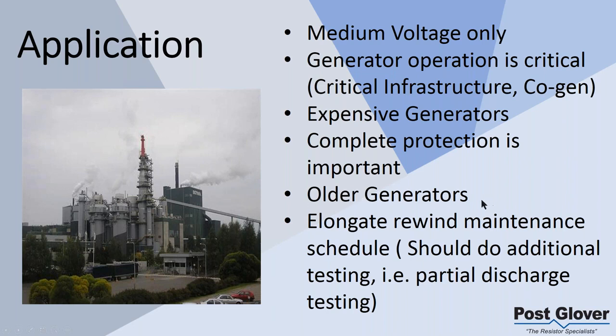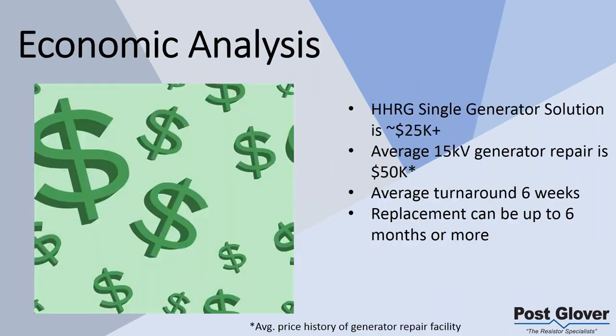Older generators, like I said, you're going to be much more likely to see this on older generators. As part of a strategy, you could elongate a rewind maintenance schedule. What does that mean? Instead of rewinding every 10 years, 15 years, based on insulation breakdown, you could do some additional testing to show you what your insulation looks like. Because you have that extra protection there, you could elongate that maintenance schedule. It's happened before. There are papers on that strategy being implemented, so I wanted to share that as well. Those are some of the reasons why you could use hybrid high resistance ground.